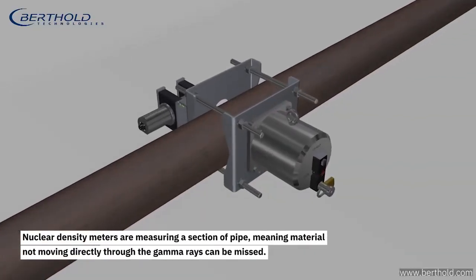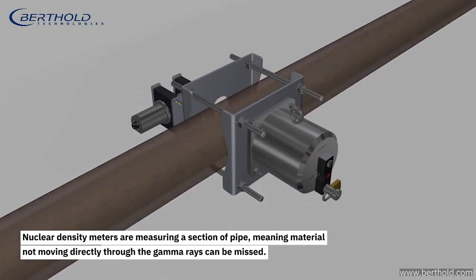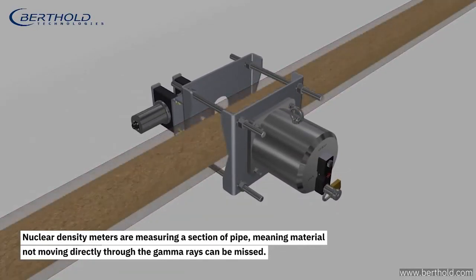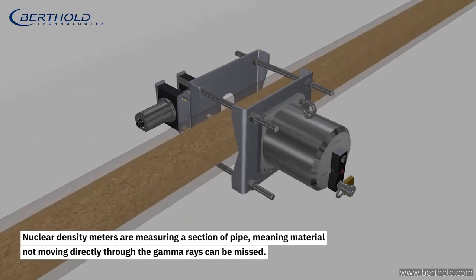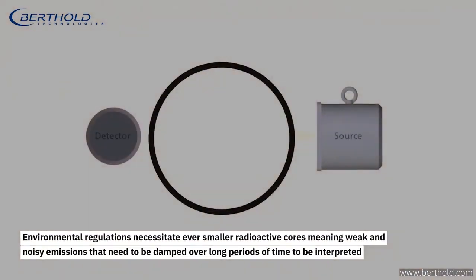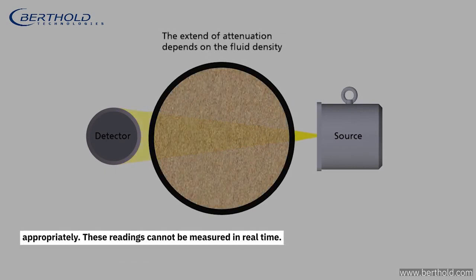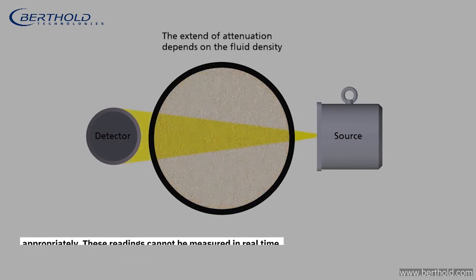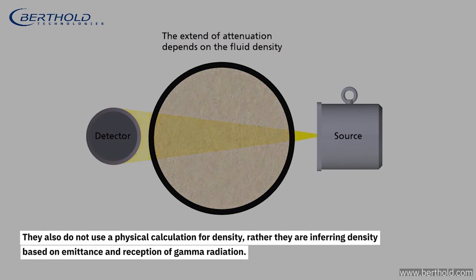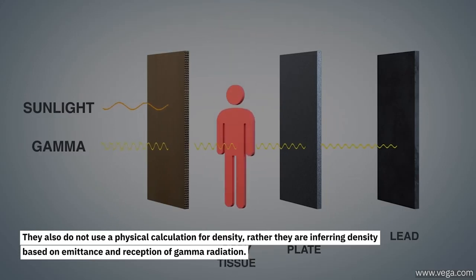Nuclear density meters are measuring a section of pipe, meaning material not moving directly through the gamma rays can be missed. Environmental regulations necessitate ever smaller radioactive cores, meaning weak and noisy emissions that need to be damped over long periods of time to be interpreted appropriately. These readings cannot be measured in real time. They also do not use a physical calculation for density. Rather, they are inferring density based on emittance and reception of gamma radiation.